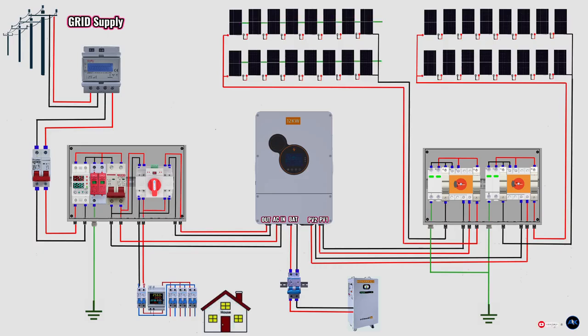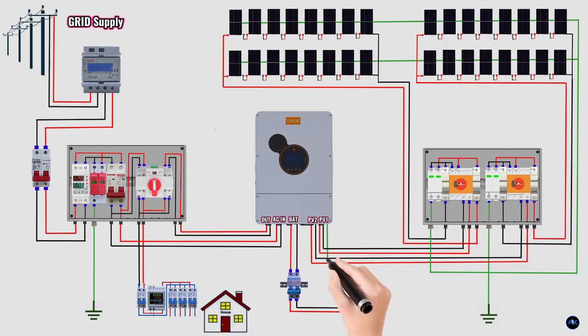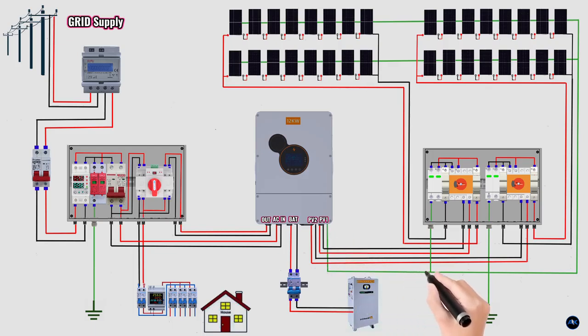Finally, we connect the earthing system. The solar panel's frames, inverter body, battery casing, DC SPD, AC SPD, and distribution board are all connected to a common earth point. This earth connection safely directs fault current and lightning energy into the ground. When all these connections are done correctly, the system operates safely, efficiently, and reliably. Every wire has a purpose, and every protection device prevents damage before it happens. This is how a complete 12-kilowatt solar power system is wired, step by step, the correct and safe way.